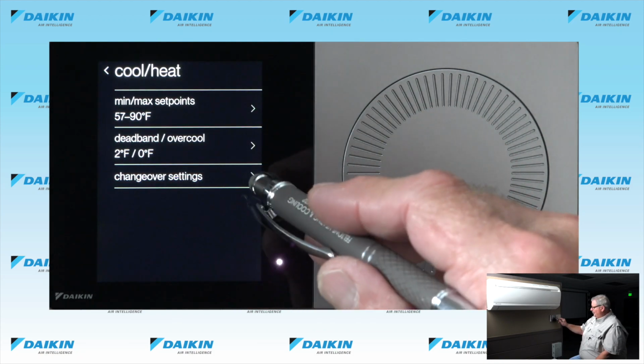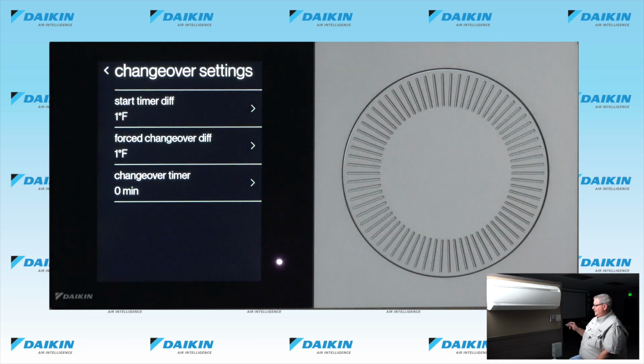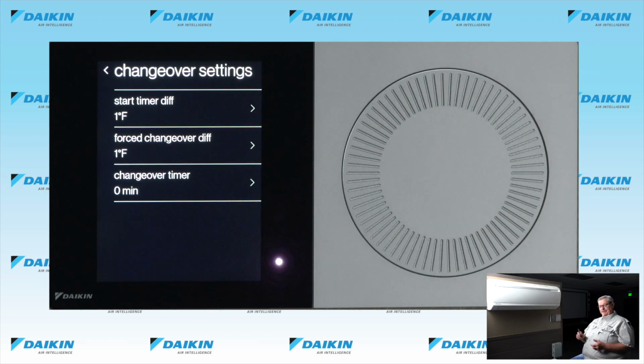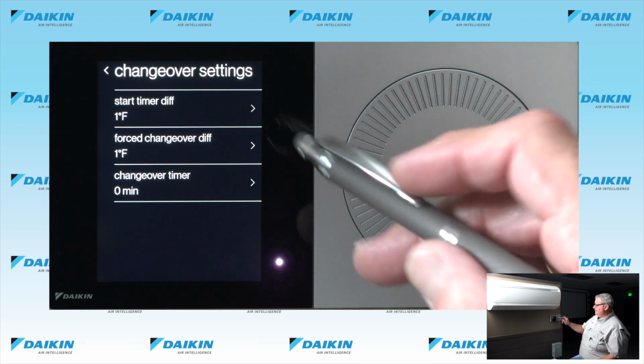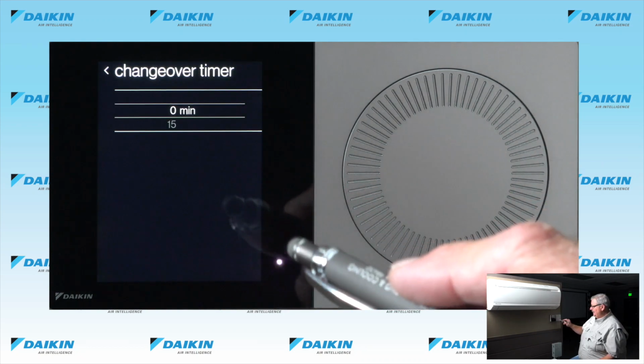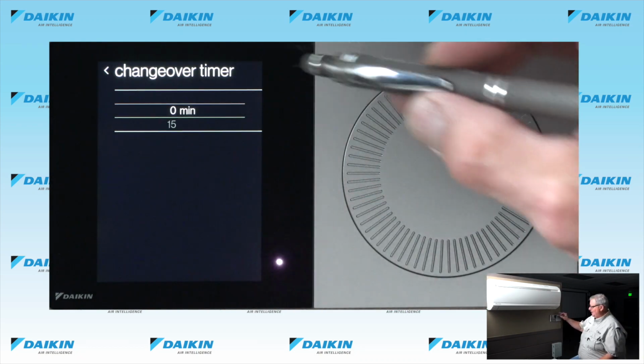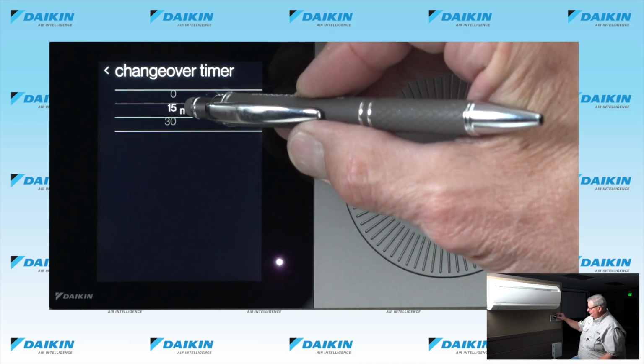And our changeover settings. Now this feature here works with that dead band. It will make the changeover once it is 1 degree past its set point. But then what happens is it will start a timer. Once that timer expires, it will make the reversing valve change. So we can make that timer anywhere from 15 minutes to an hour. I always suggest the 15-minute mark.